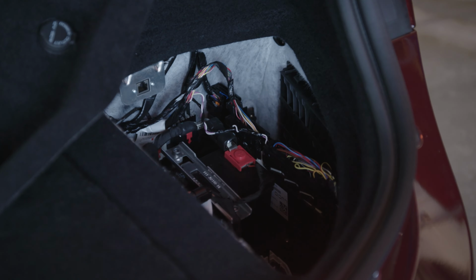With the application of water, the smoke or gas indication of lithium-ion battery fires typically remains very light colored or white in nature. This is often misperceived or misunderstood as steam as a result of cooling the batteries. To differentiate between steam and lithium-ion gas production, 4 gas meters should be placed into the gas clouds to evaluate for the presence of CO. CO components will not be present in the production of steam. Once the batteries have been actively cooled and CO values are not present in the 4 gas meters, then the thermal imaging cameras should be relied on, and the batteries should maintain a temperature below 200 degrees F and continually reducing before the vehicle is considered to be in a relatively safe state.